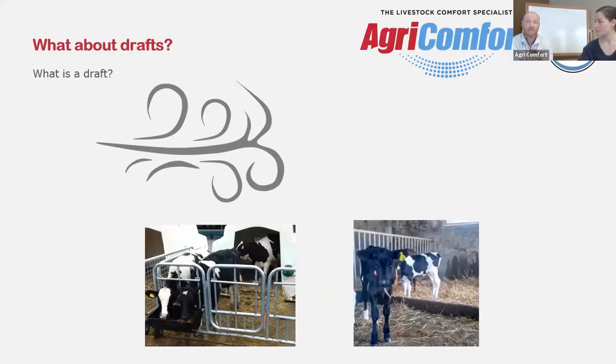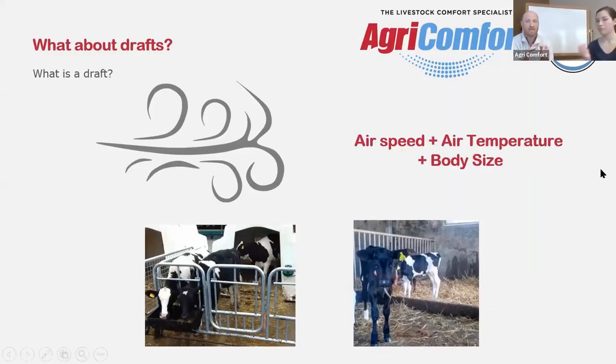But now the problem is it's more complicated than that. If that is by definition a draft, is it necessarily a bad thing? What if it's 90 degrees Fahrenheit out, and that calf is standing in 100 feet per minute airspeed? Technically, that calf is subject to a draft. But in the farmer's mind, a draft is something bad. So what we have to tease apart is, a draft, with a negative connotation, is really a function of airspeed, air temperature, and body size.